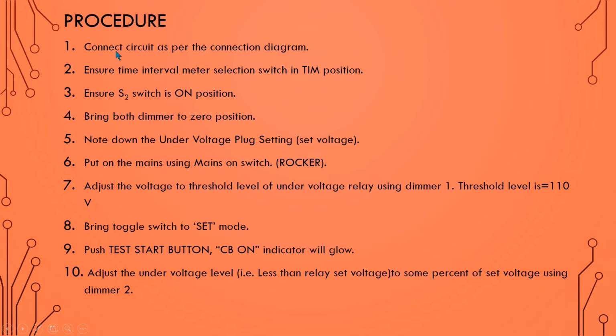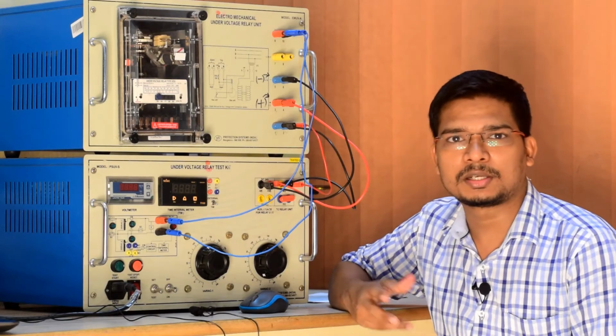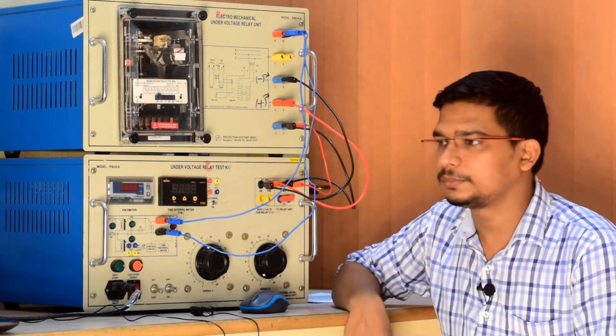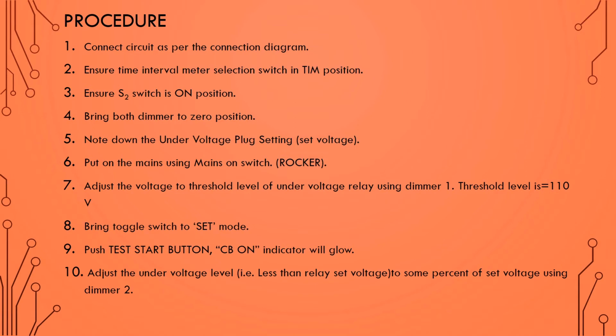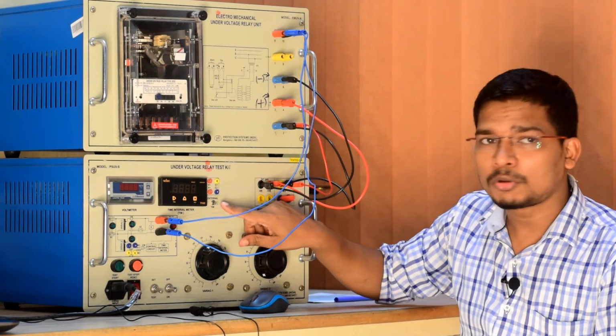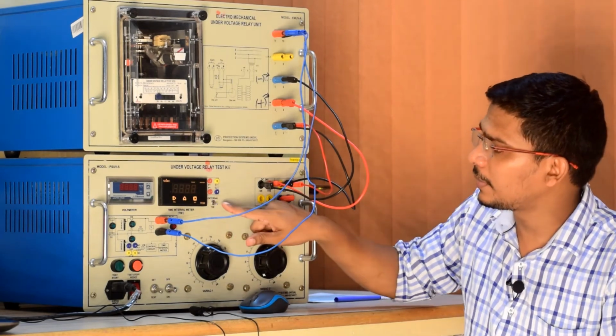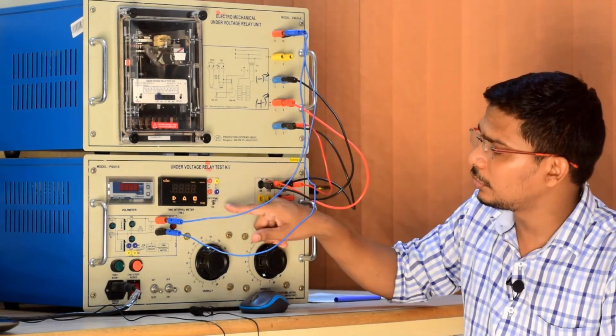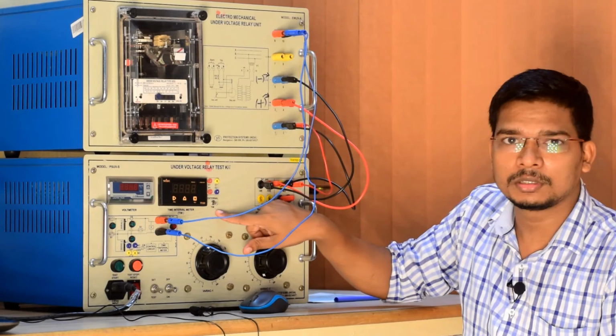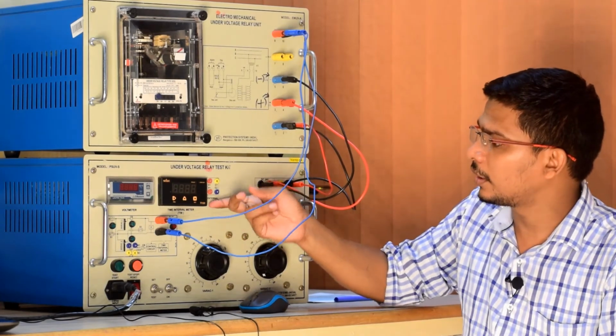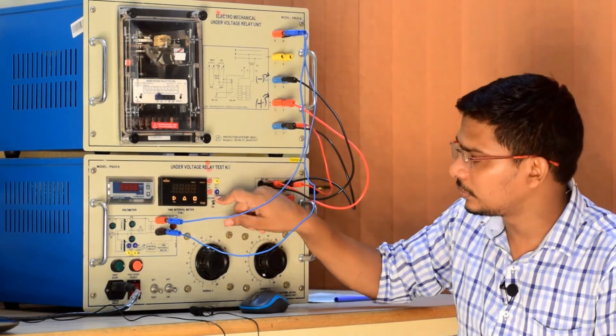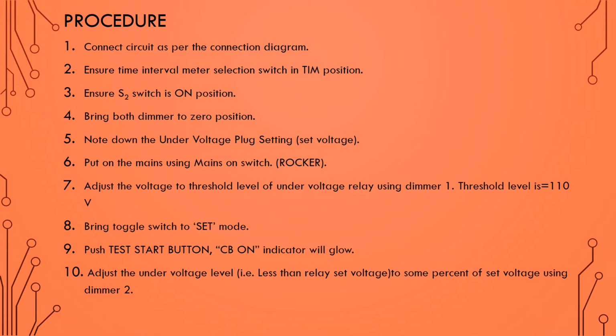So the first step is to connect the circuit as per the connection diagram, as you have connected. Next, ensure the time interval meter selection switch is in TIM position. As you can see, this is the time interval meter switch. This should be in TIM position. The bottom position is TIM and the up position is external. So this will be in TIM position.